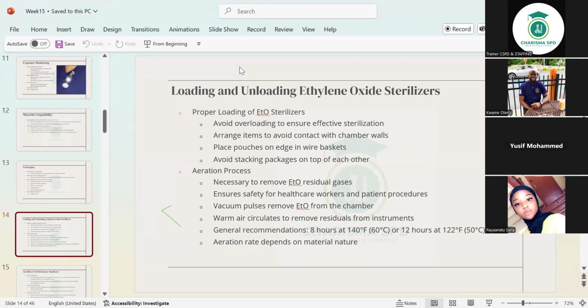Okay. So the next one is that vacuum pulses remove ETO from the chamber. Remember the system is coming to an end. So after the aeration, the vacuum pulses remove the ETO gas in the system. It's removed out. Then warm air goes in, circulates to remove the residuals from the instruments. That's how the aeration process goes. As soon as the ETO is vacuumed out, the warm air comes in.